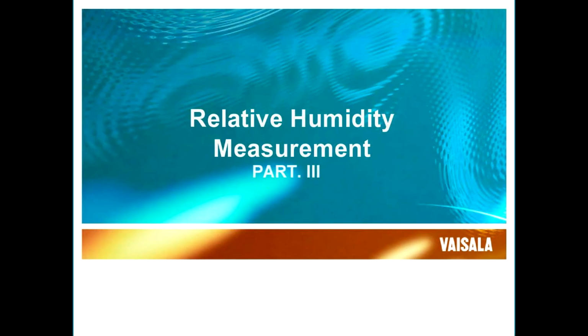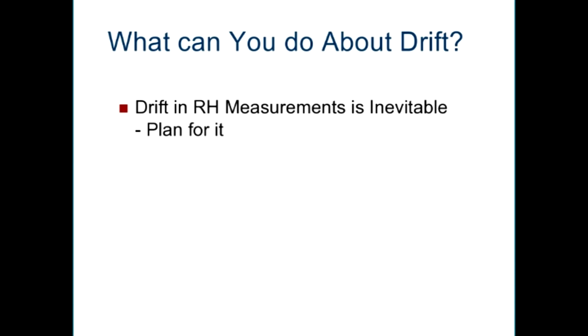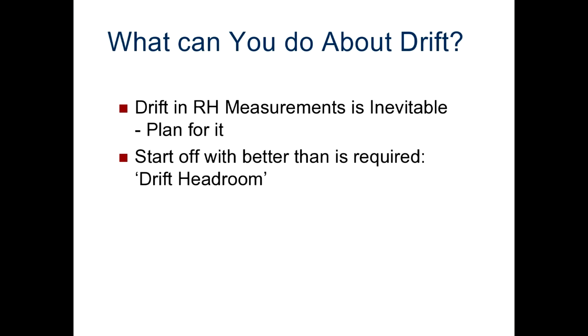So what can you do about drift? Drift in RH measurement is inevitable, so plan for it. Start off with headroom, better measurement accuracy than you need. If you need a 3% measurement, then one should not start off initially with a 3% measurement uncertainty or accuracy of the instrument because you have no room to drift.